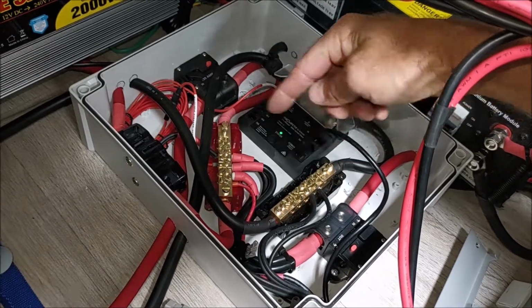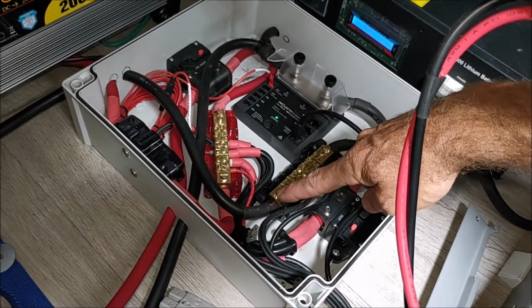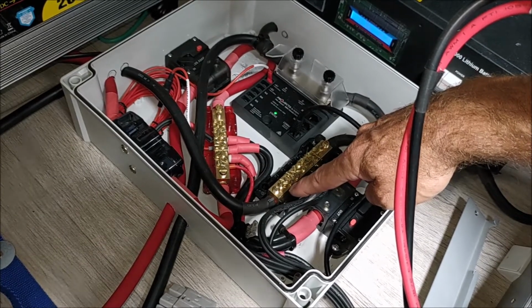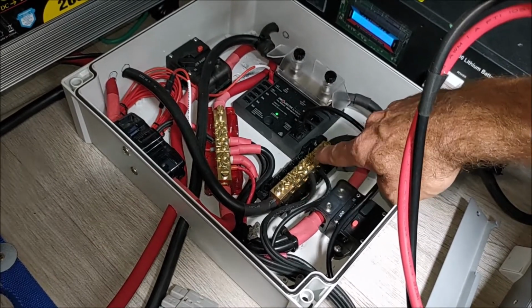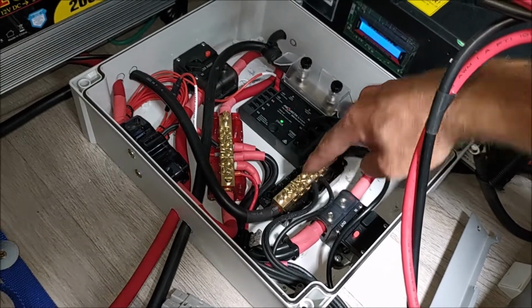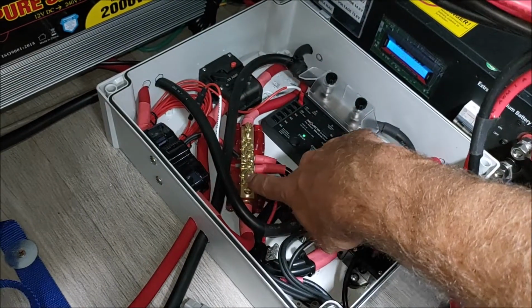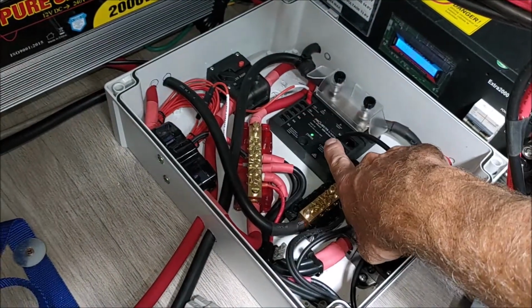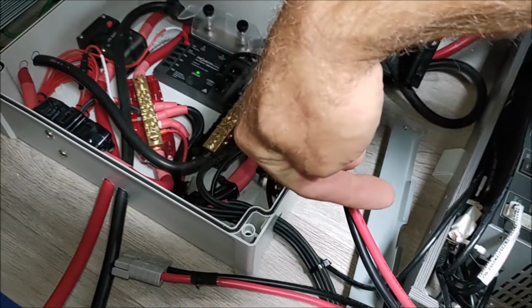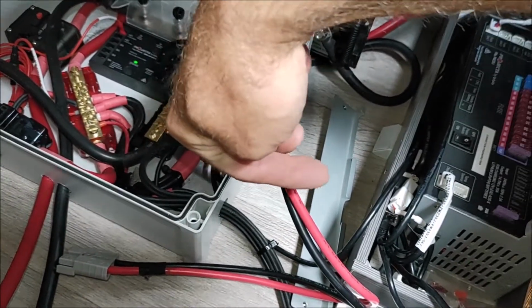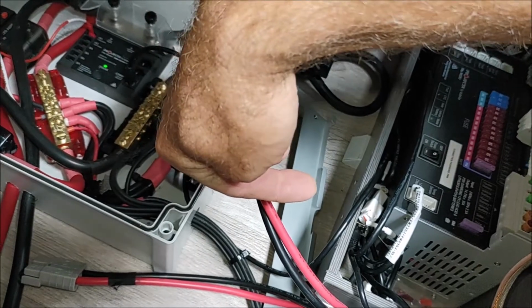So obviously the DC-DC charger - I've got the direct connection for the 12 volts for the hot water unit through here, that's 25 amps, which runs through these bars as well. Any inverter you want to run needs to go through the shunt, because it won't run through this unit - only low current loads run through this unit.